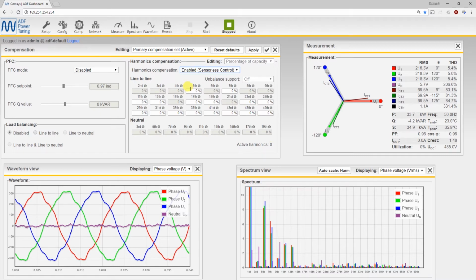The question is just how much harmonic current are you giving the system to operate here. This is now a 120 amp system, so if I would add 10% on the 5th harmonic, that means I'm able to give out 12 amps to compensate the 5th harmonic over here. So we're gonna just start the filter quickly, then we're ready to operate.